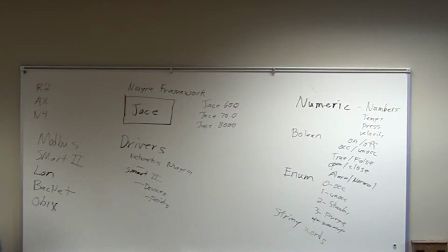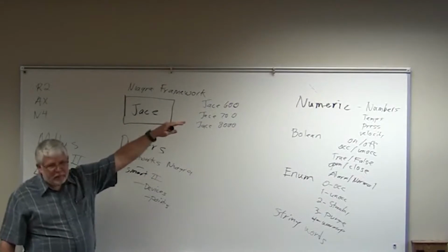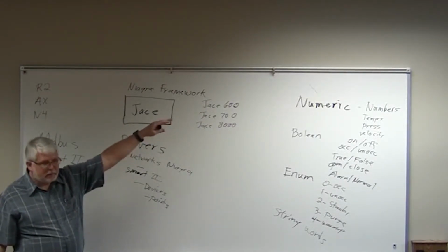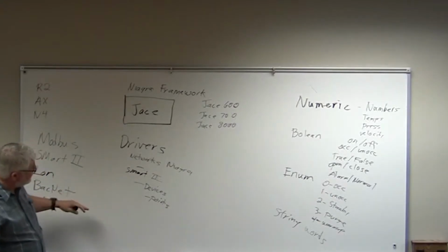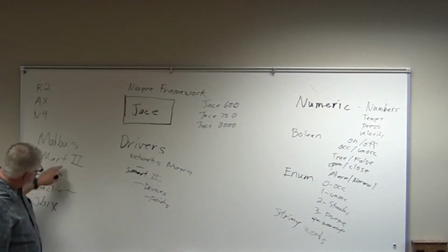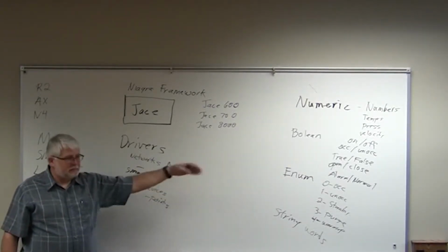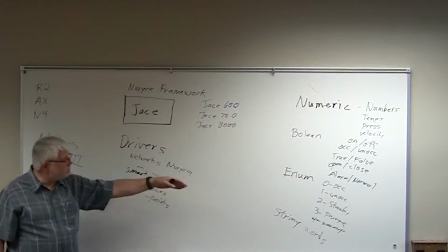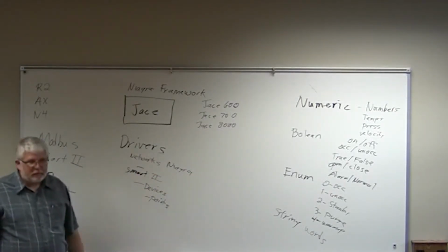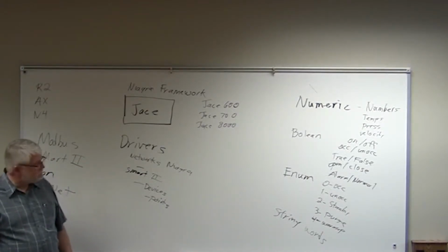So our zone temperature for the Smart 2 guy is going to come in as a numeric object. Occupied, unoccupied modes from a Smart 2 will probably come in as an enum, because it has multiple states. Fan start stop will come in as a Boolean point.